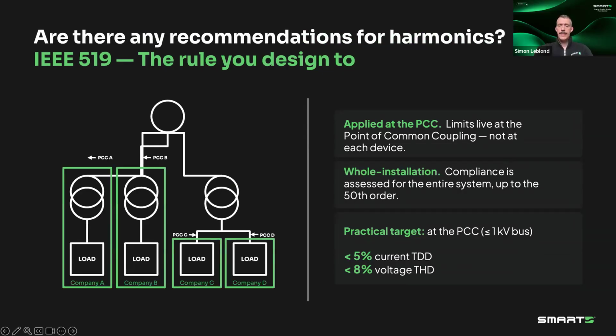First, IEEE 519 is really assessed at the point of common coupling. So it's not a device level rule. Even if you had a drive without a DC choke that is generating 70% THDI, you could still be 519 compliant if the rest of the system is clean enough. And the inverse: if you have low harmonic drives everywhere, your system could still fail if you have other sources of noise and your point of common coupling is small enough. So when you think IEEE 519 harmonic study, you do need to think of the complete installation.